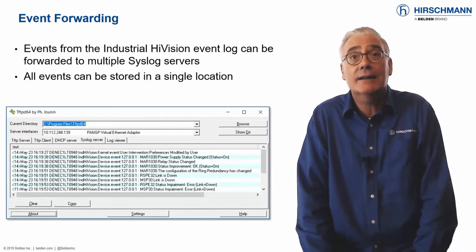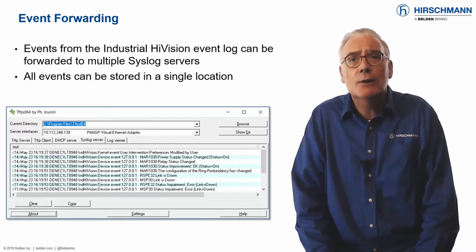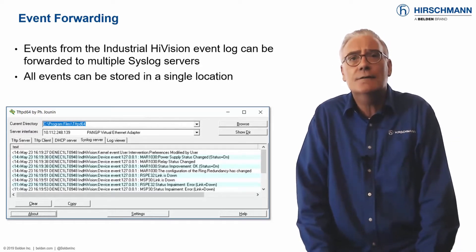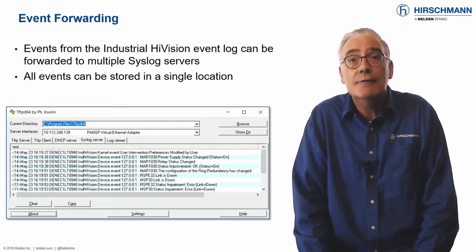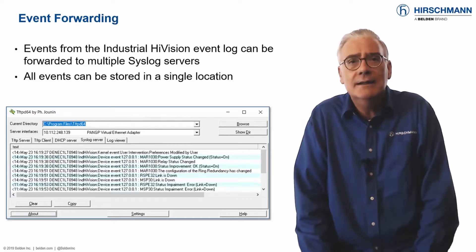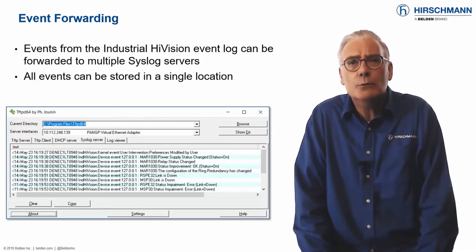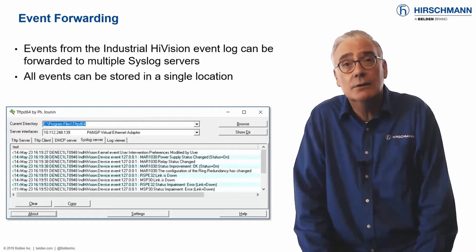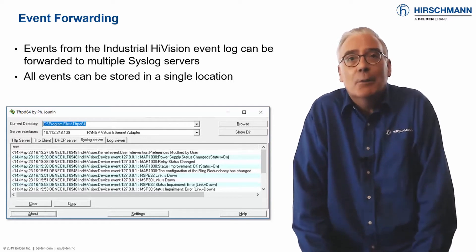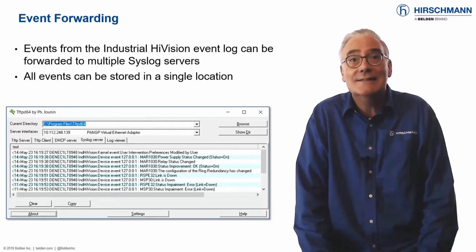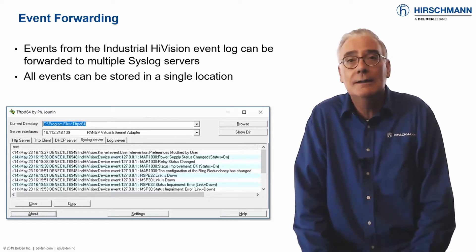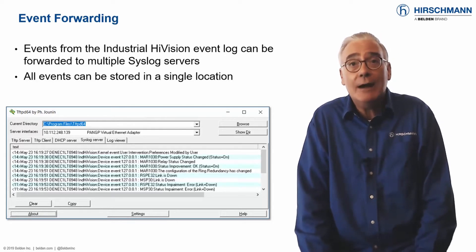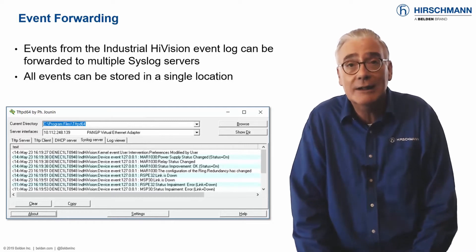Industrial HiVision provides two powerful options to forward events to one or more central syslog servers. First, all internal events can be forwarded, so events relevant to Industrial HiVision itself, such as user logins, are stored. Second, events about network devices can be forwarded. This is useful if your network devices do not support syslog, and also valuable if you do not want your devices to send their own syslog messages outside the local network. Storing all your messages centrally will allow you to take advantage of modern techniques such as event correlation.